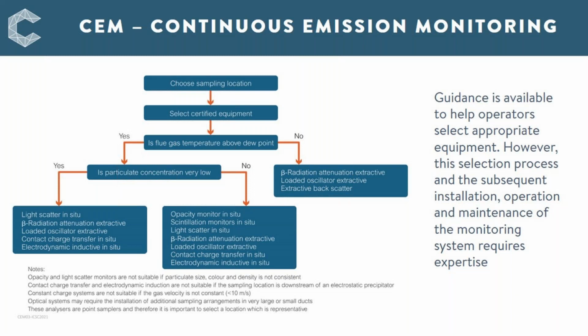This diagram shows a simplified flowchart of how to select and install a CEM system for monitoring particulate emissions. The first consideration is, of course, the sampling point. And even this is more complex than you might think. The sampling port, the little hole in the stack that the probe will go through, must be in an accessible location on the side of a stack.